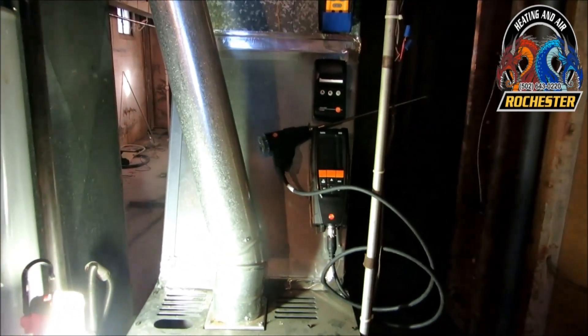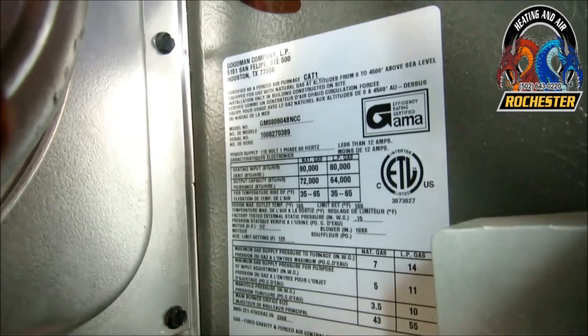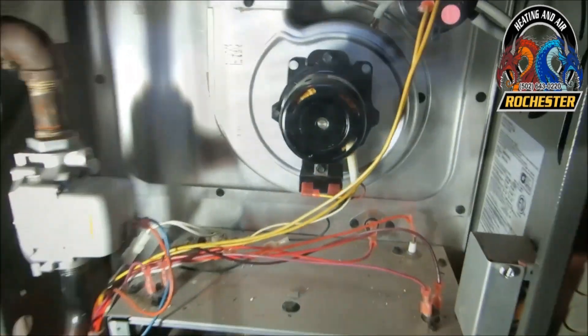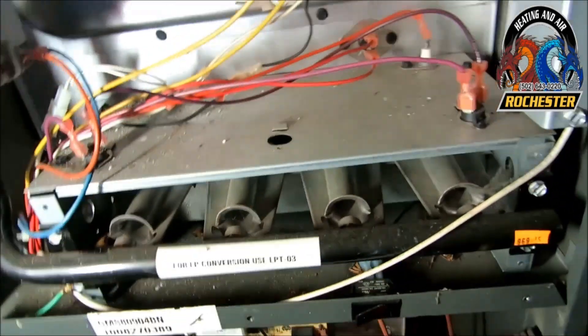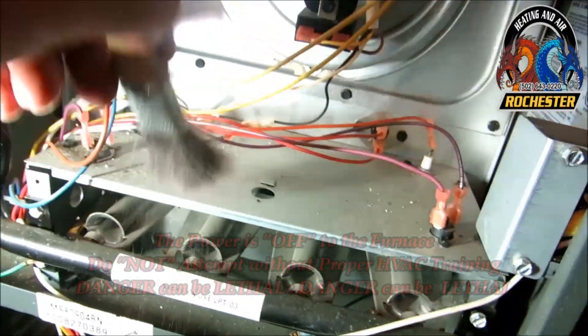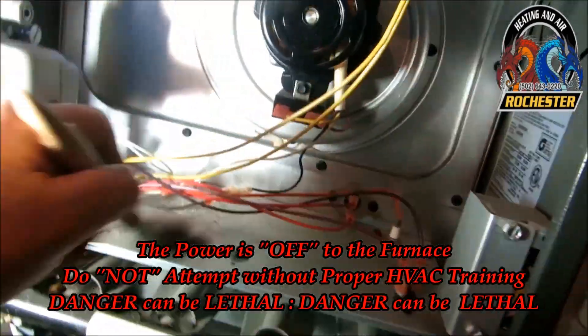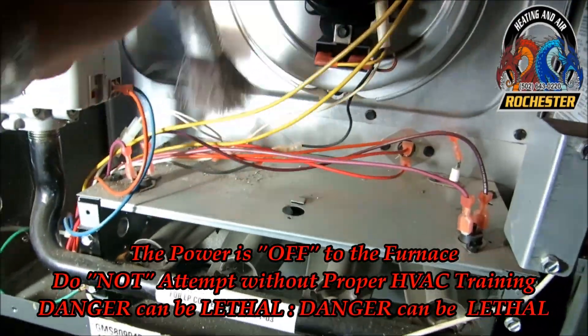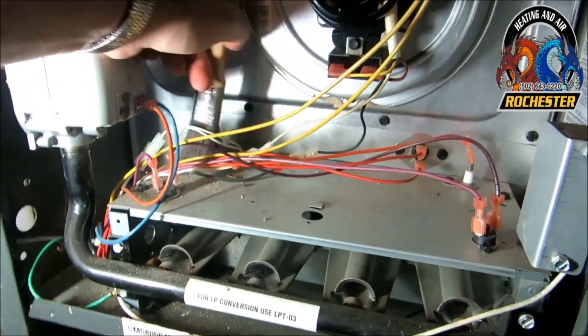All right guys, let me get the door off this thing. It's really not that dirty to have not been serviced in quite some time, but I went ahead and broke out the Ridgid and got myself a little brush. I like to just kind of get in there with that a little bit — that way I don't really bump into the wires as bad — and then I'll just vacuum the rest of it up. This is also giving me time to let my hot surface igniter cool off as well.